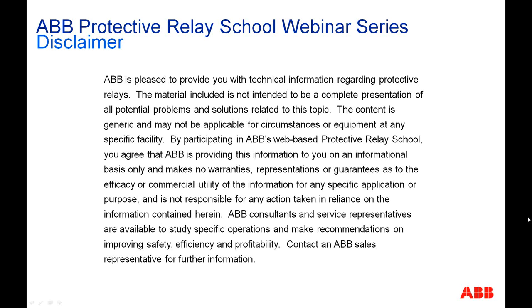Another question is that line differential protection practical on MV lines such as 33 kV? Also, what are practical cost efficient communication options? Well, the most economical solution would be a direct fiber optic link between the two ends or three ends, and up till 150 kilometers you can actually use a direct fiber optic link. And if the distance is more than that, then you can use the repeaters, for example, or you can use the other communication medium like G703 or X21.